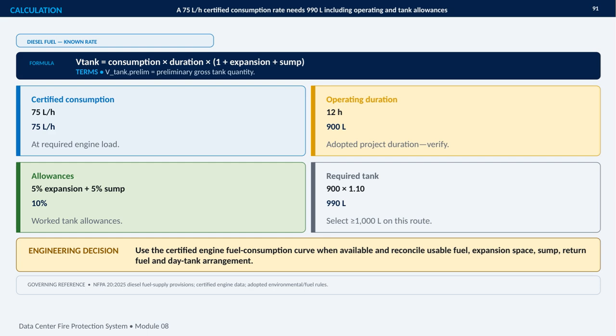The practical engineering decision is to select a tank of at least 1,000 liters on this route, while verifying the adopted project duration. Where available, the certified engine fuel consumption curve should govern the calculation. We also need to reconcile usable fuel, expansion space, sump capacity, return fuel, and the day tank arrangement. The governing references include NFPA 20:2025, certified engine data, and applicable environmental and fuel requirements.